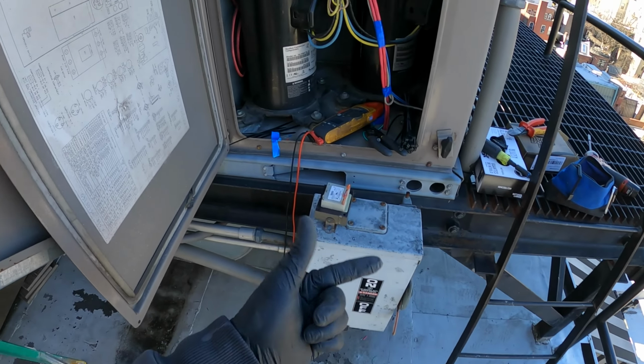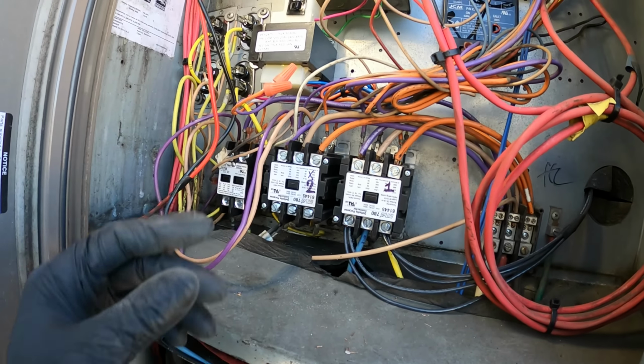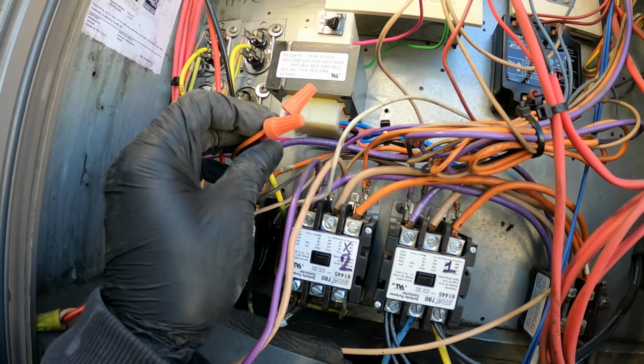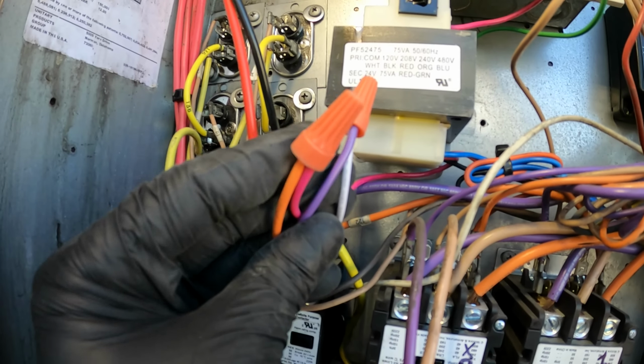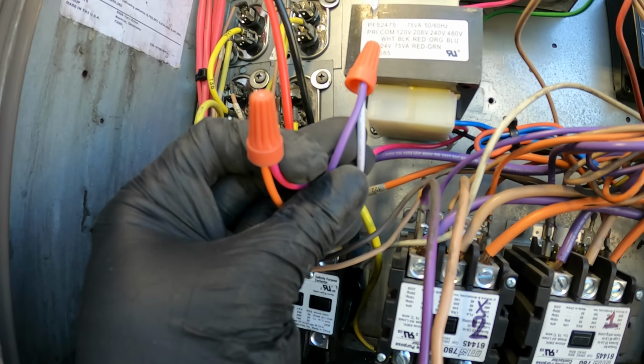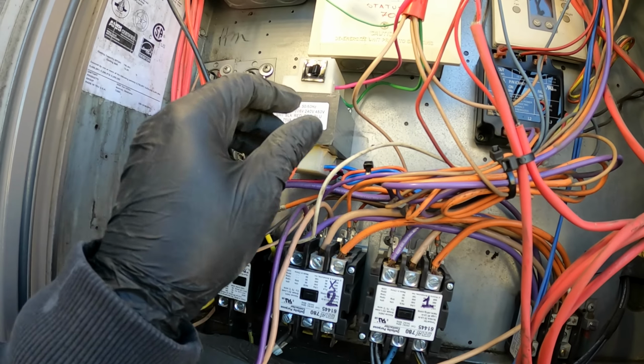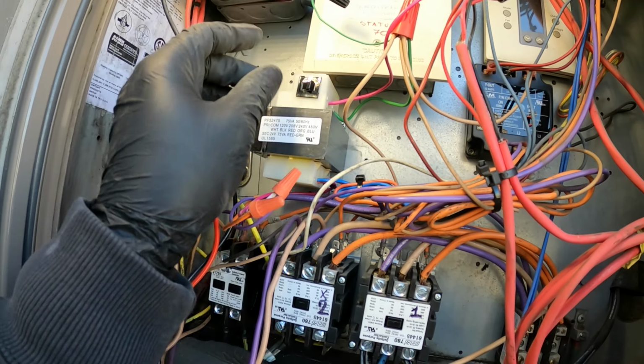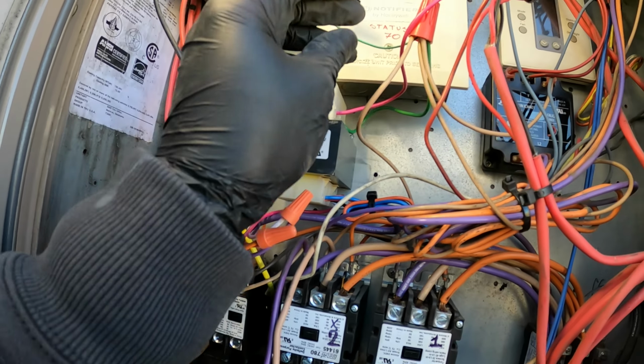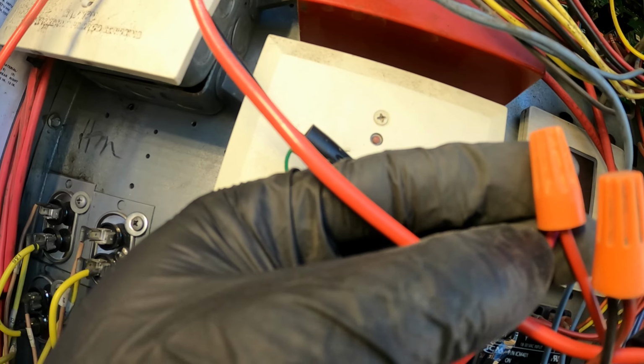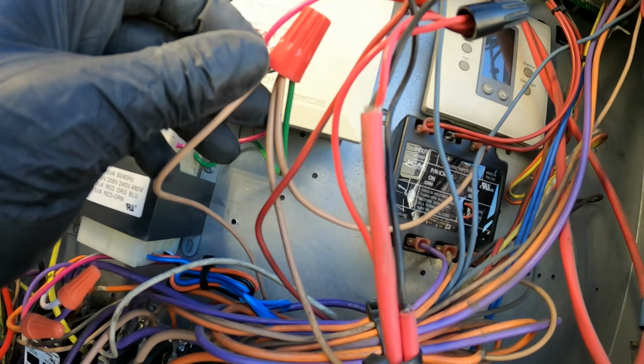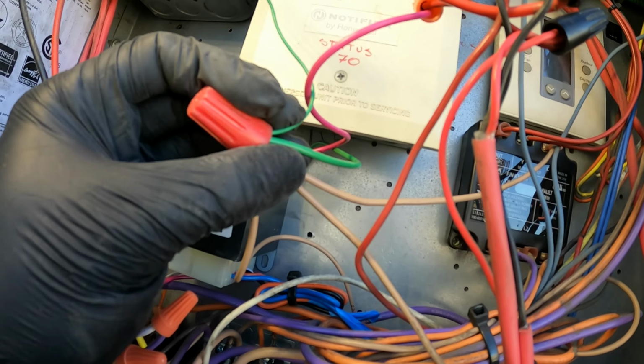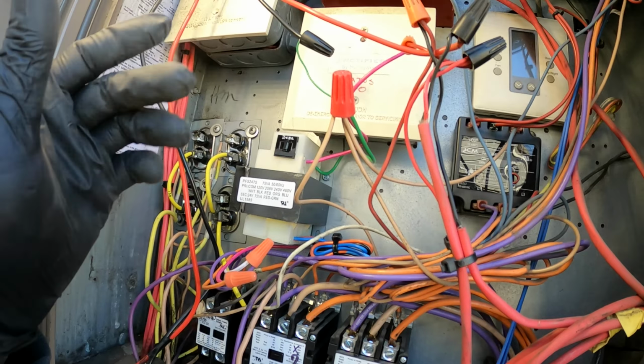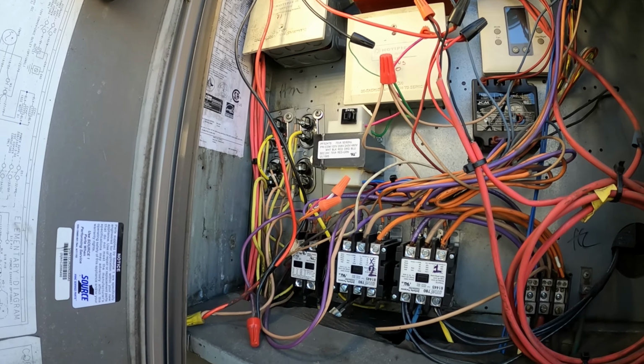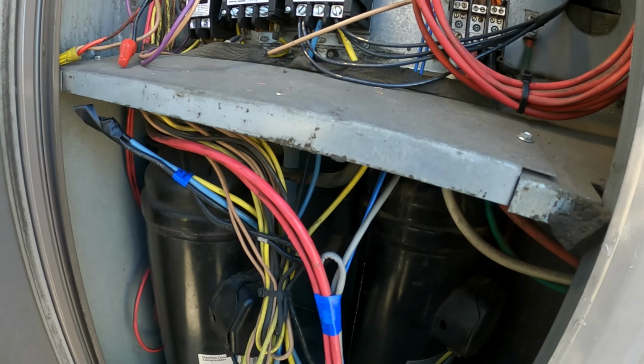We're pretty much good from here. What we're gonna do is turn the power on, and you're gonna want to have 208 volts between these two connections, between your white and your red. Then you're gonna want to check for 24 volts between the other two connections, between your red and your green area. Between those two, you should have 24 volts. And that's pretty much it, but that is how you upgrade a transformer.